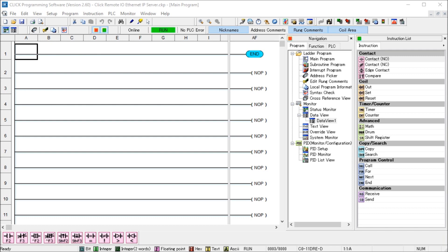Implicit messaging, which we'll do today, means the data messages are streamlined and the device is configured ahead of time to know what to do with the data. This is used for time-critical messages and functions like a typical scanner-adapter relationship — so remote IO like we're going to be doing. Implicit messaging is real-time and copies data with minimal additional information because both ends already know exactly what each byte and bit will do. The Click PLC will be the EtherNet/IP adapter and the Productivity will be the EtherNet/IP scanner.